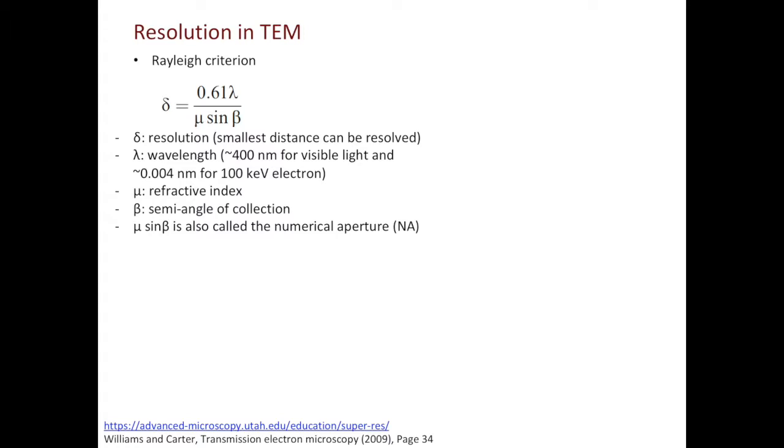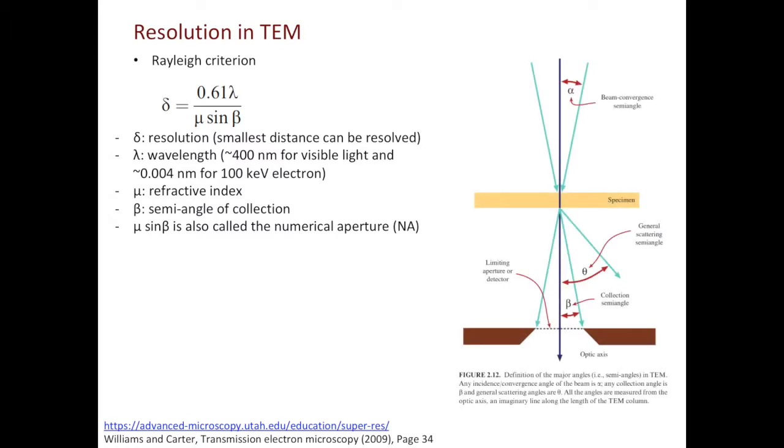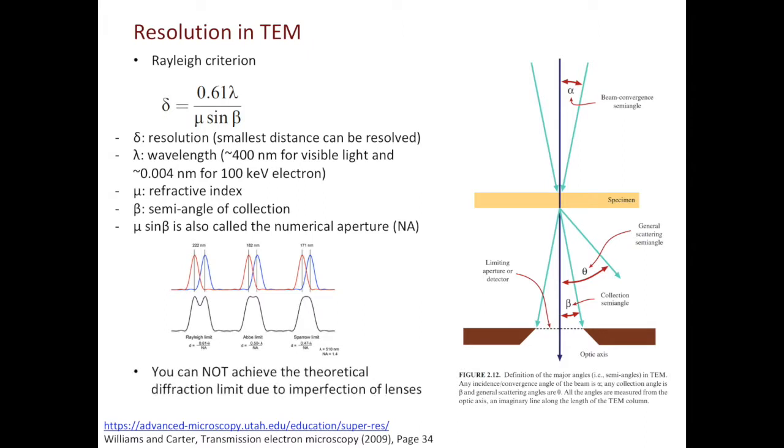Just a couple more words on the angles alpha and beta. They will appear again and again in the future videos. Alpha is called the convergence semi-angle. You can tune that by converging or spreading out the beam. Beta is called the collection semi-angle. And the value of beta is determined by the size of the aperture. Note that the Rayleigh criterion is not the only criterion you can use. There are other criterion you may consider when calculating the resolution. A very important point to make is that you can never achieve the theoretical diffraction limit of electron beam. This is due to the imperfection of lenses. Spherical aberration and chromatic aberration are examples of lens imperfections.